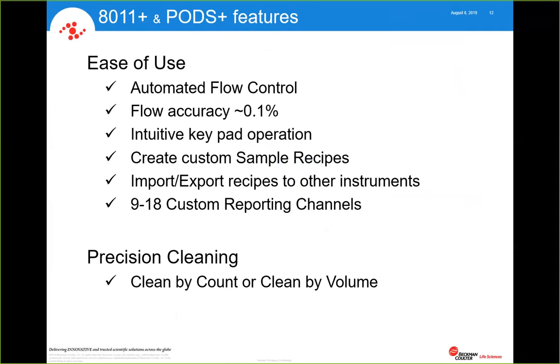So if you have multiple systems and you create a custom recipe on one, it's a very simple matter to export that to a USB stick and take it over and deploy it to your additional systems without having to rewrite it at each station. For the custom reporting channels, if you want to report to a custom reporting standard, the PODS Plus allows up to 9, where the 8011 Plus allows you up to 18 individual channel sizes.